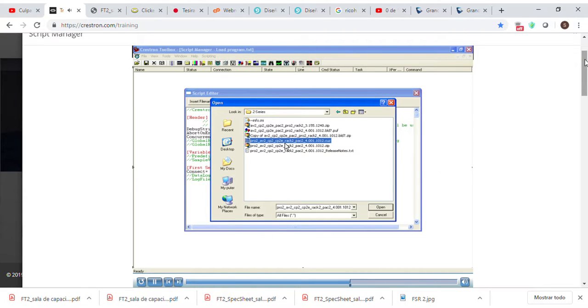A quick note here about this file. If you download the new operating system file from the Crestron website, it will be in the format of a PUF file, meant to be used with the PUF update tool. But when writing a script to accomplish this, you will need to extract the CUZ file from the package. You can do this by creating a copy of the PUF file and then changing the PUF extension into a .zip, and then using WinZip to extract the CUZ file. Click the button to see how this is done.